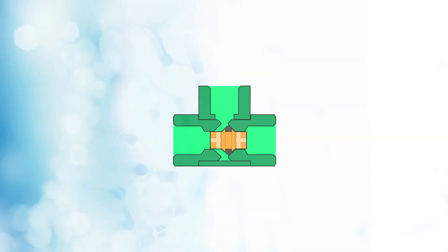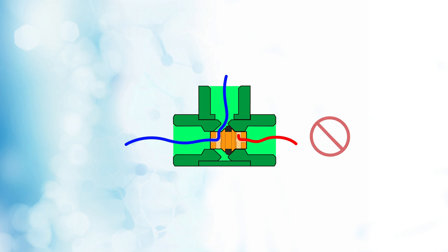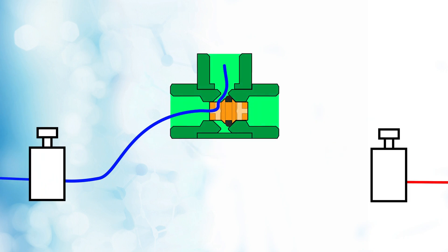A common reason is that you could still have pressure on the opposing port. Again, a shuttle valve is not a selector. It is looking for one signal at a time, not two. Check to see if you have pressure in the opposing port that is somehow getting trapped in the system's pneumatic circuit.